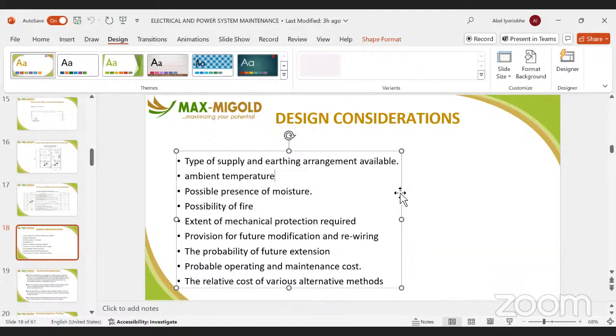Knowing fully well that over there they have a maintenance plan, but here we don't have maintenance plan as our culture. So you install it, the developer is happy, it's installed. But when you want to maintain, you have to go and rent a crane just to replace a bulb. Because you did not budget maintenance cost, bringing in a crane or scaffold may require breaking walls so the crane can move in. That's too much cost. So you must consider operating maintenance cost. If replacing a bulb worth 700 or 7,000 naira means bringing in equipment costing over 500,000, does that make sense? It doesn't make sense. You have to consider all of this.